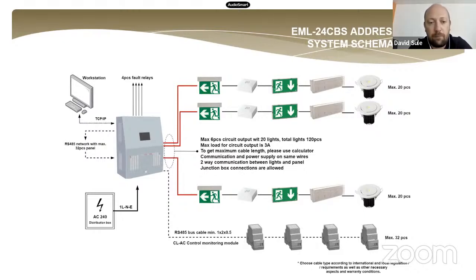The panel has a maximum of 6 circuit outputs. We sell only one type of panel, so when you order a panel, it will have a maximum of 6 circuit outputs, not 4 or 2, it's 6 outputs every time. All of these outputs are limited with a 3.15 amp glass fuse, on the positive and the negative cable too. And the limit for this output is 3 amps. Each output can control a maximum of 20 addressable luminaires, and the total capacity is 120 luminaires.